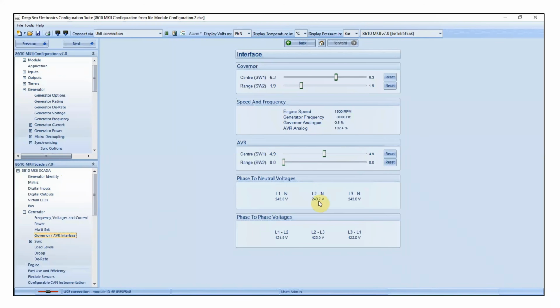Remembering that as we increase switch 1 of the AVR, the voltage increased, so there's absolutely no need to output reverse on the AVR. But the voltage hasn't gone all the way to 264 because our AVR's switch 2 is too small. So next, as you can see on the video, we're going to increase the switch 2 value until we get an AVR analog percentage of 80%.